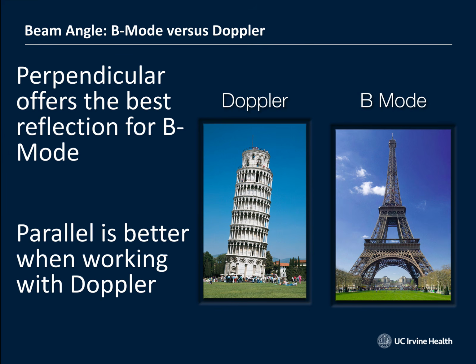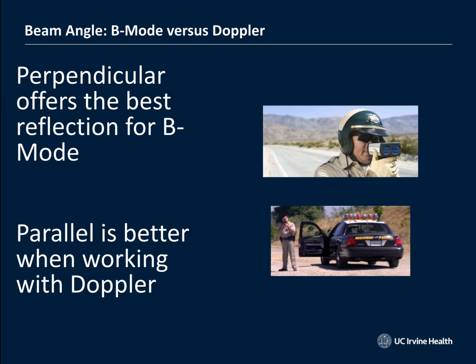But it's important to remember the difference between B mode and Doppler when it comes to beam angles. When it comes to B mode, perpendicular is going to offer the best reflection and the best images possible. So when you really want to look at something, forgetting about Doppler for a second, on B mode or brightness mode, then you want to be perpendicular to that organ that you're trying to insonate. But when it comes to Doppler, it's different. You need to be off axis and think more about being parallel.